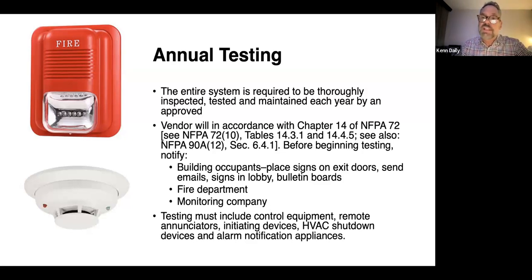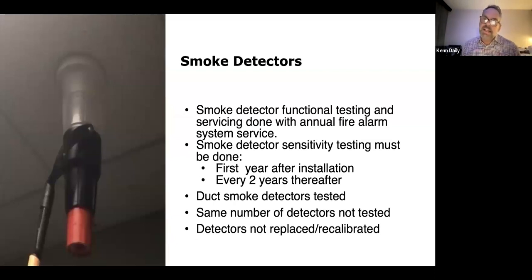Functional testing is different than sensitivity testing. Functional testing is basically pushing the button or making it go off, making sure that the alarm or the function itself is appropriate and is working according to the way it was designed, engineered, and then installed at your building. And then smoke detector sensitivity testing is where, every 2 years, the first year after installation, but most of us are in a two-year cycle now, you have every smoke detector in your building sensitivity tested, and that's sensitivity to parts per million of smoke. And so you can't use magnets. The magnetic test is not appropriate. So this is that cone test where they take a cone of smoke and they smoke your device.